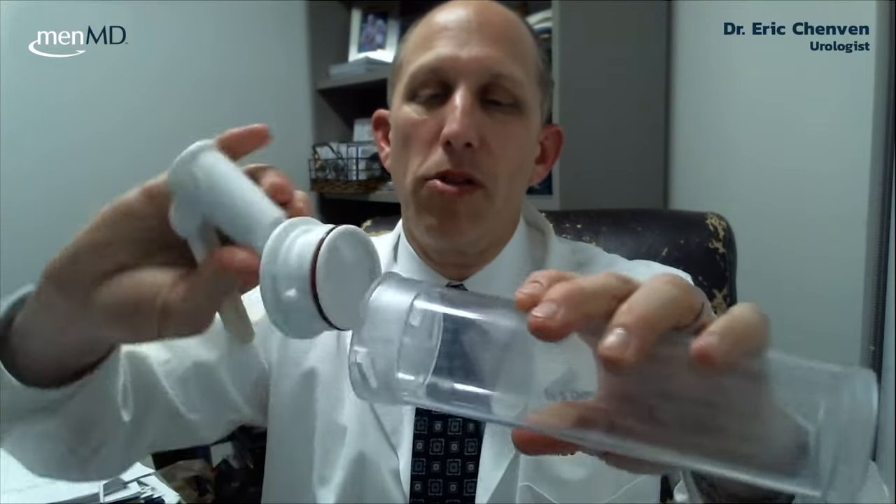As they showed you in that video, lining things up — you have on each side one of these little tabs. There's one on the other side as well, and there are two slots where they go into. It doesn't matter which orientation; it's a circle, it spins around. You push straight in with the tabs and then slide and twist it all the way around to lock, so the little nub on the white pump end slides over onto the cylinder. That's also going to ensure that the red rubber ring is in far enough to create a seal and a vacuum.